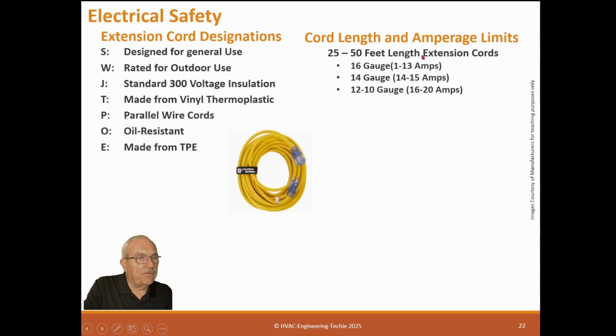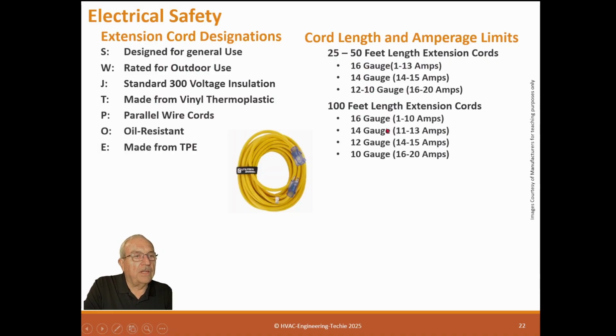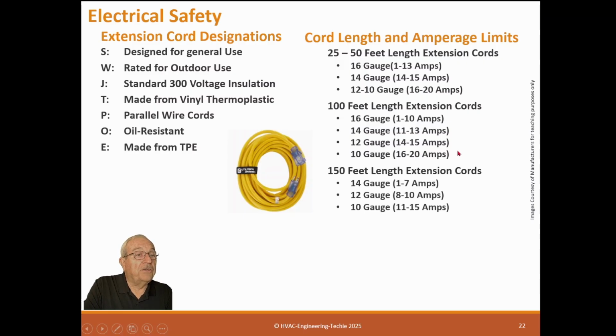Cord length and amperage ratings. So for a 25 to 50 foot cord, a 16 gauge will carry 13 amps, a 14 gauge 15 amps, a 12 gauge 16 to 20 amps. I'm not sure about a 10 gauge. For a 100 foot length, 16 gauge is 10 amps, 14 gauge is 13 amps, 12 gauge is 15 amps, 10 gauge is 20 amps. For 150 foot cords, 14 is 7 amps, 12 is 8 to 10 amps, 10 is 15 amps.